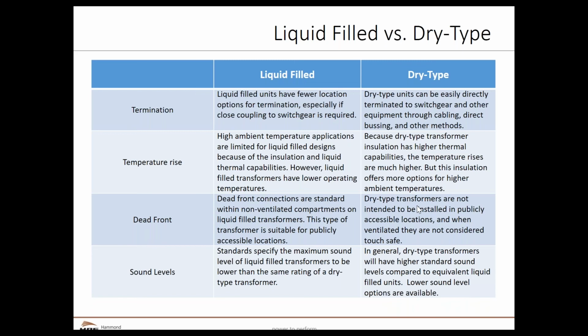Sound levels, again, liquid filled will be a little bit quieter than dry type by the very nature that the core and coil is submerged in the liquid, and that helps deaden the sound. You can do lower audible noise transformers with dry type, but they tend to cost a little bit more and be a little bit bigger. However, because liquid filled transformers don't have all of the temperature rise options that dry type do, oftentimes with liquid filled it might be more common to employ cooling fans, which can greatly increase the dB level of that particular transformer.